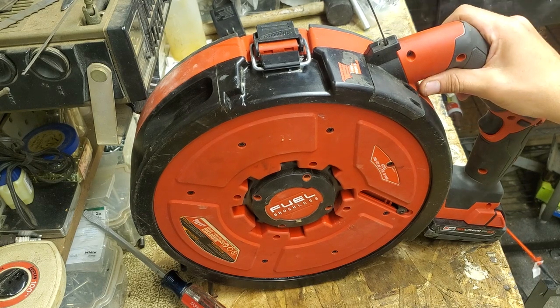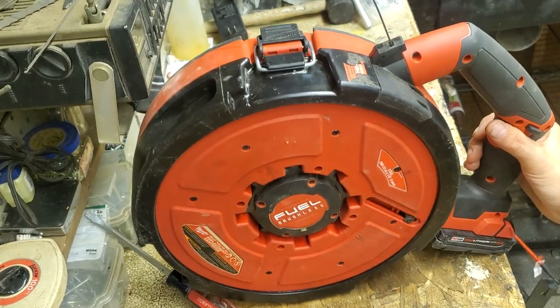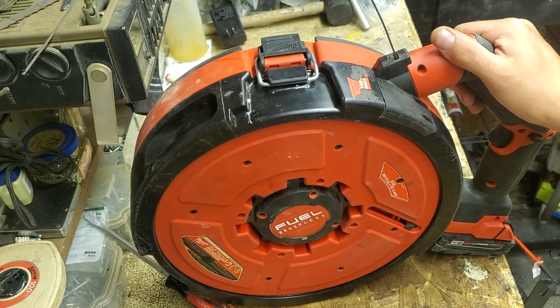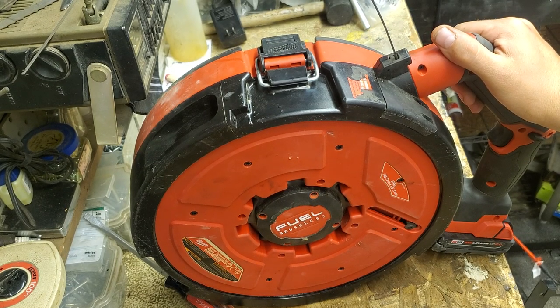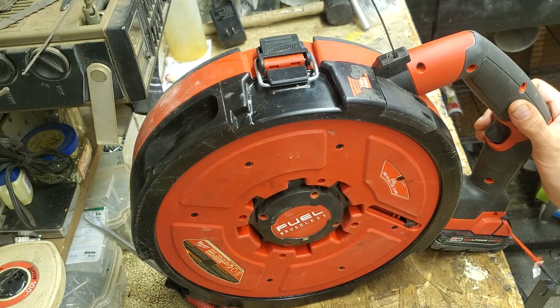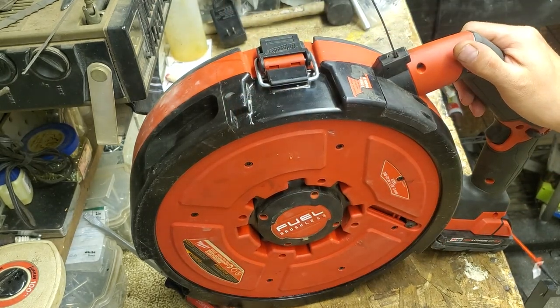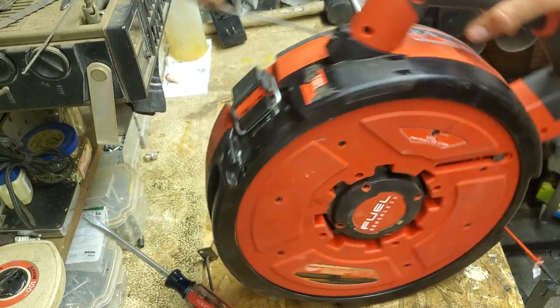After that it just didn't impress me. It made a clicking noise every time I used it and I just started finding flaws. Using this on underground conduits is a huge no-no — just don't do it. I let some co-workers borrow it for indoor two-inch EMT conduits and they ended up leaving it completely uncoiled, with like 10 runs to do. They said it was too slow, so they left the whole thing strewn around the electrical room and just kept shoving it in by hand. They were kind of missing the point.